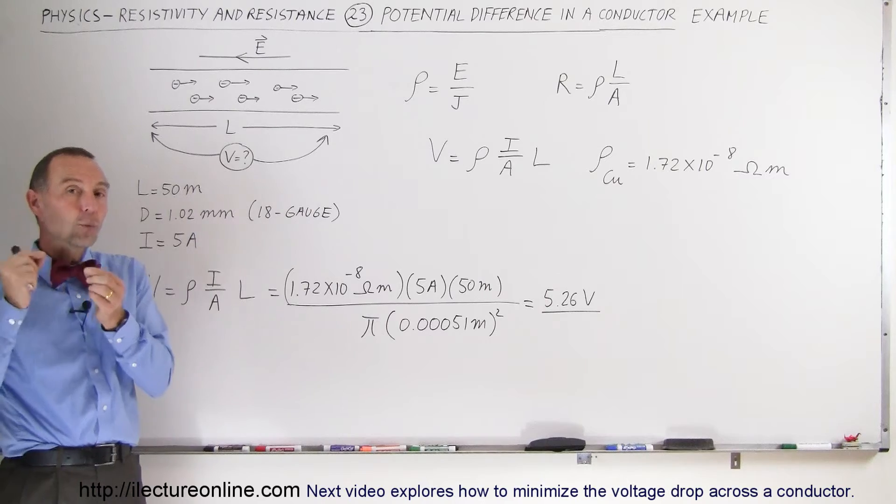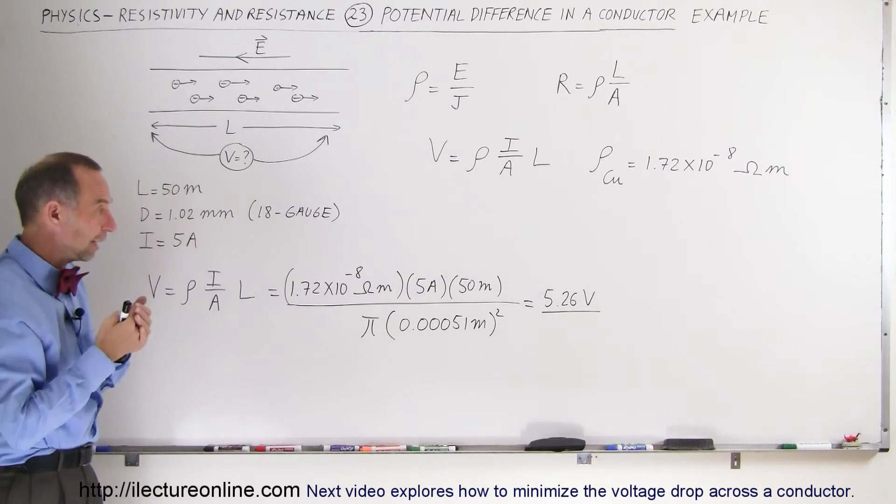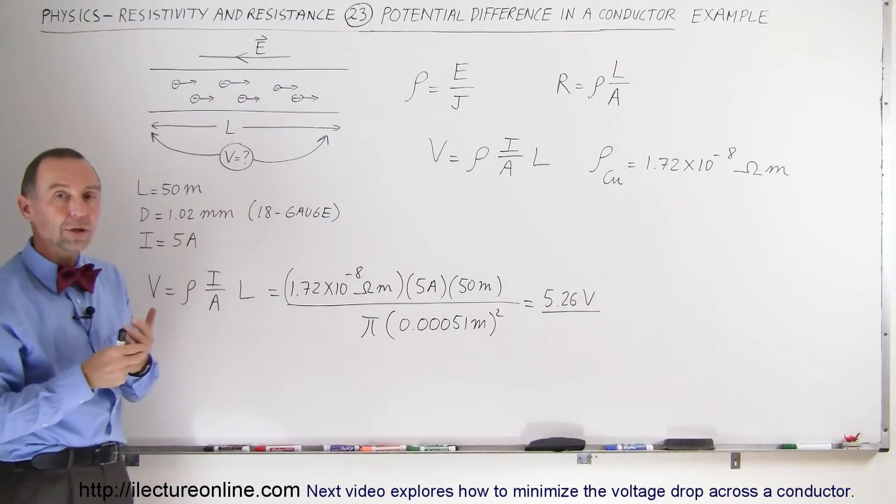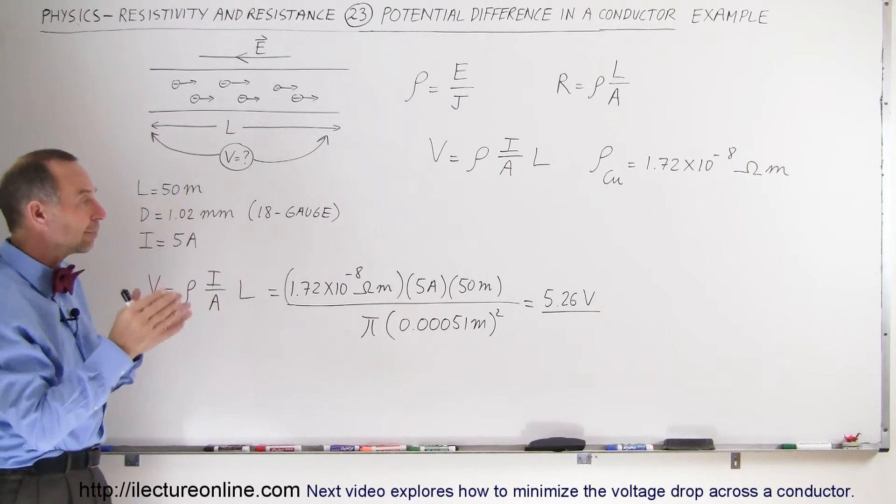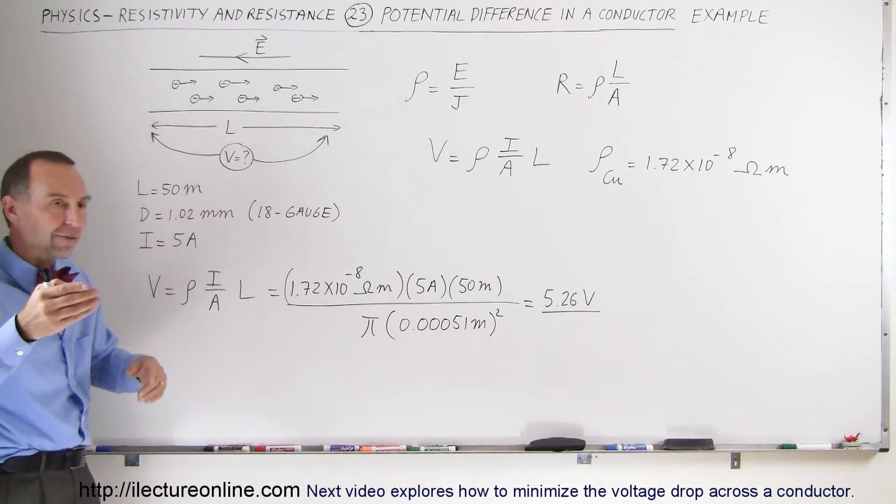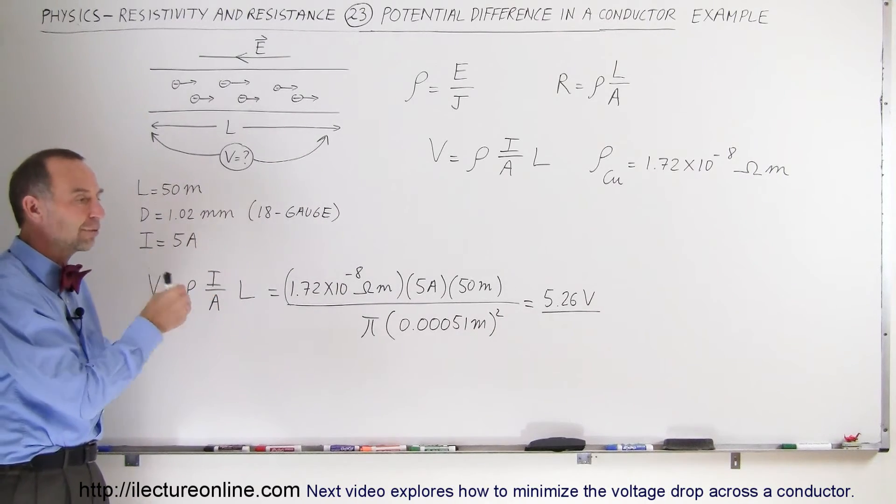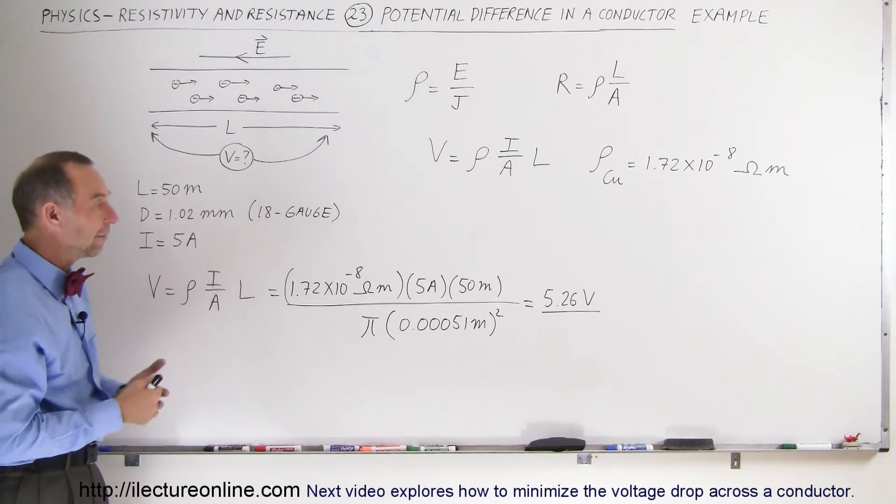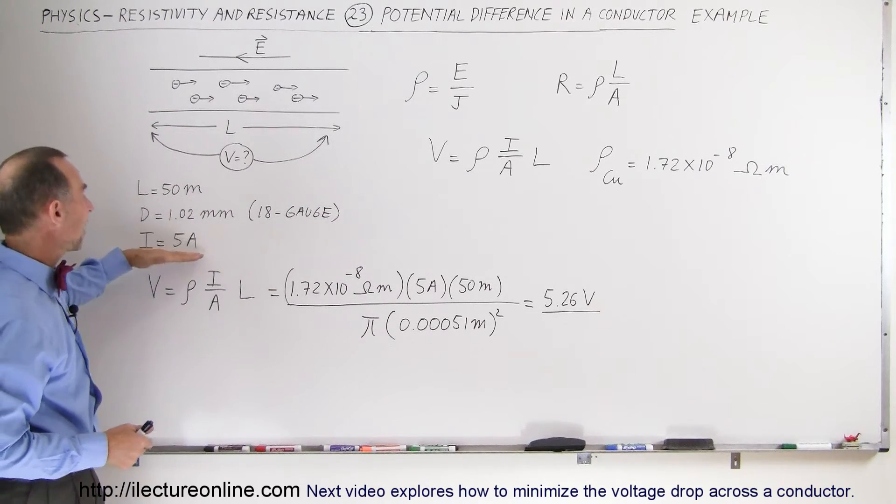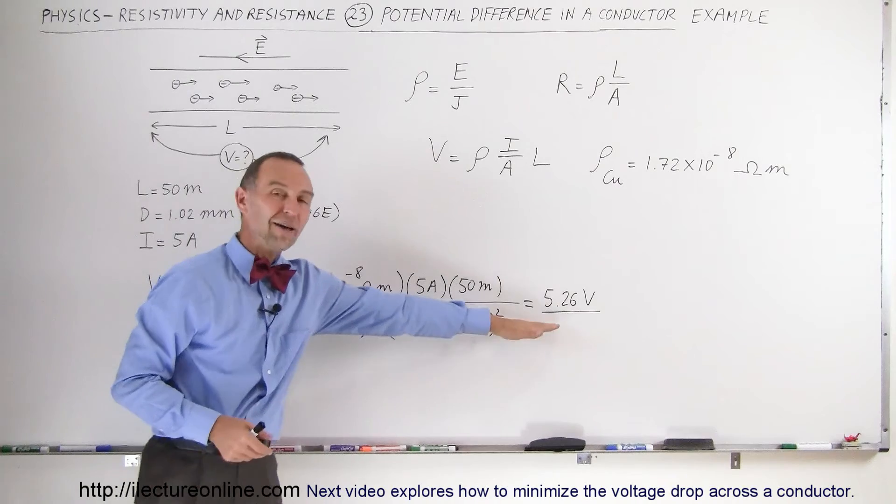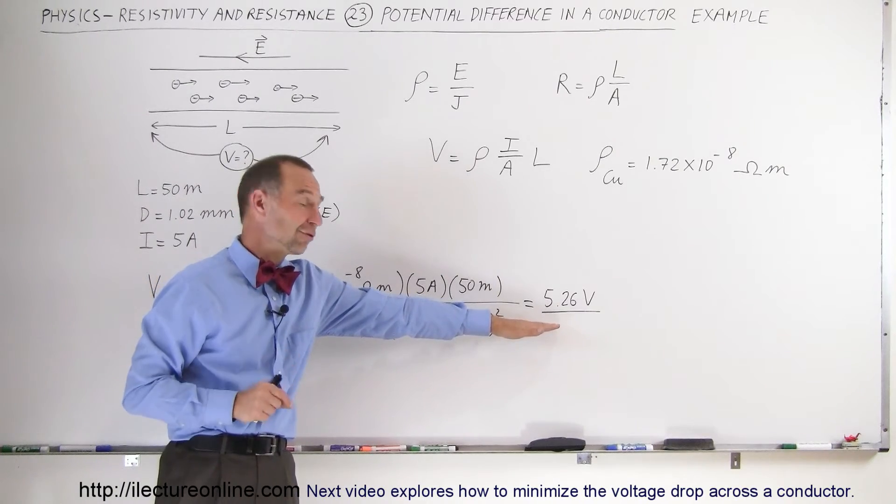And so if you run a long wire from the inlet box at the house and let's say that we have 100 feet or 150 feet of wire before we get to the room that you want to have outlets at and you run a 5 amp current through the wire, you lose 5 volts across the wire which is kind of interesting.